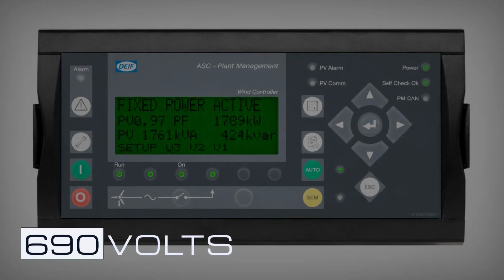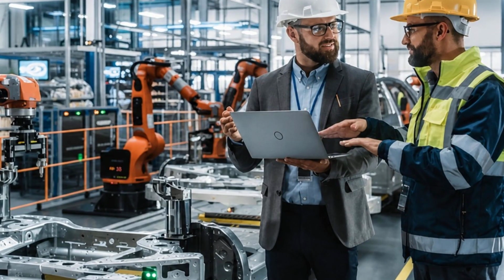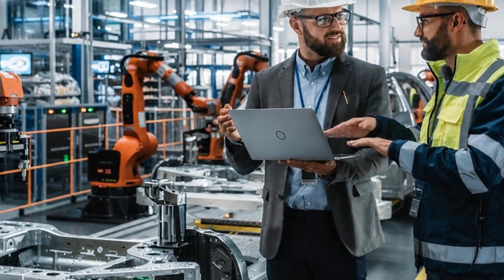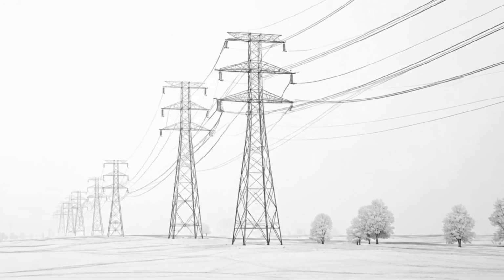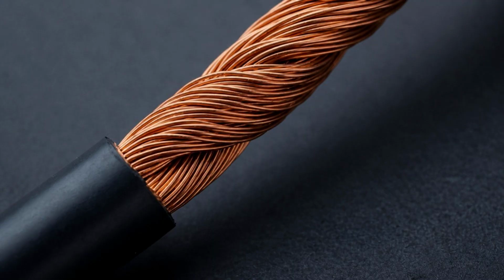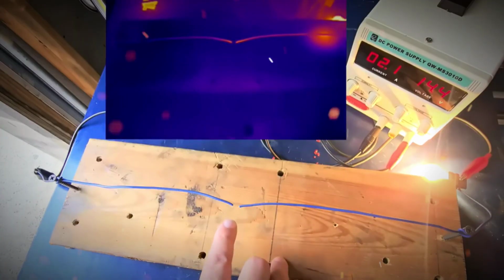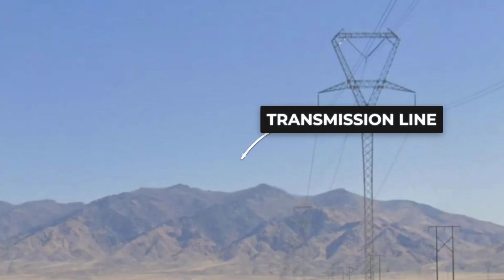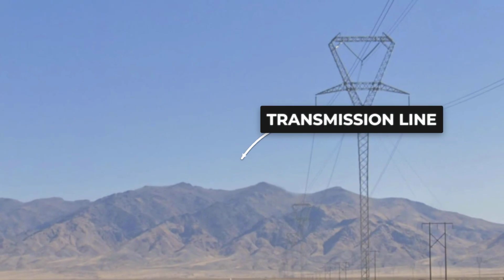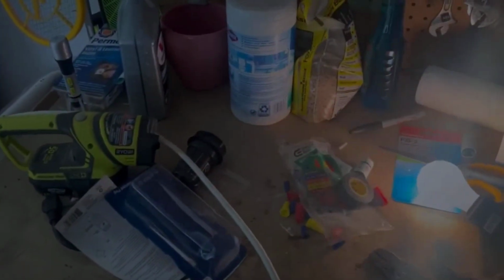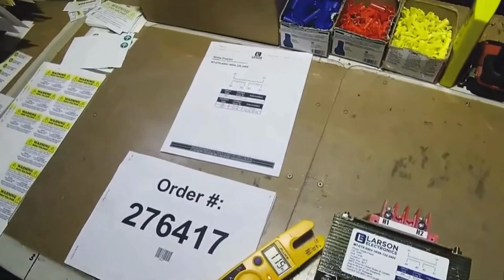The generator produces roughly 690 volts, enough to power a factory floor. Nowhere near enough to travel any real distance. At 690 volts, the current required to carry meaningful power is enormous, and current generates heat. Send that electricity down a transmission line toward the nearest town, and resistance bleeds it dry. Energy converted to waste heat, mile after mile, until almost nothing useful arrives. The voltage is strong enough to exist, but too weak to survive the journey.